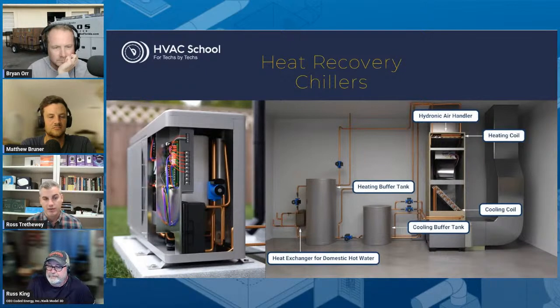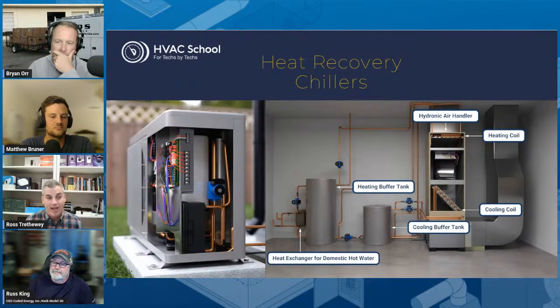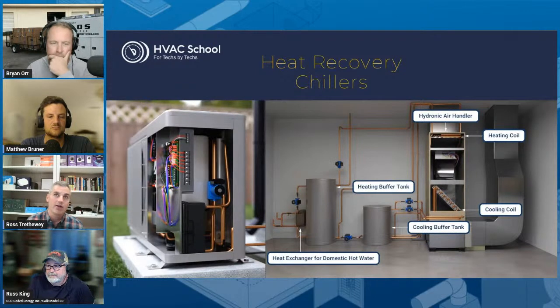And so now, like you said, if I can do a self-contained box that's outside that has a really great refrigerant in it, I don't have to worry about the refrigerant phase-outs in the future. I don't have to worry about changing my 410A line sets when R32 and other refrigerants come down the line. I can have it all self-contained in one box outside. I just take that box off, put a new box back in, reconnect it, and all of the indoor stuff, the piping, the ductwork, can stay the same. So you get inherently future-proofing with this type of system as well. So we're designing systems with this right now.